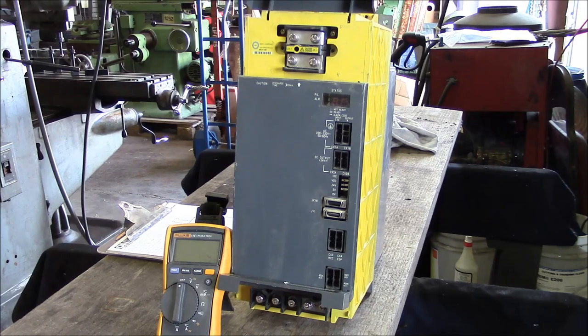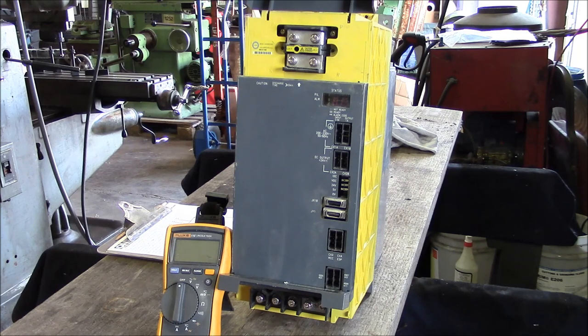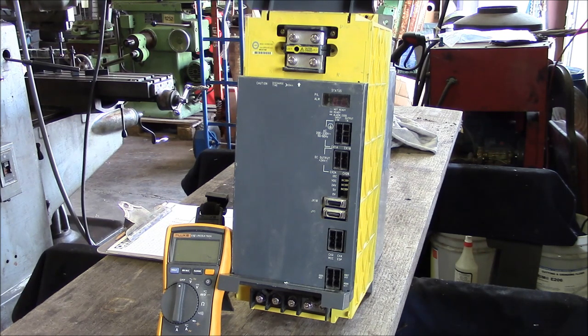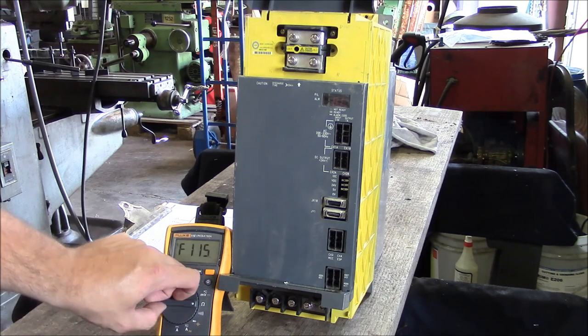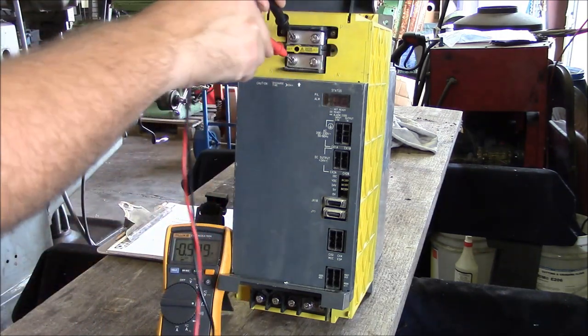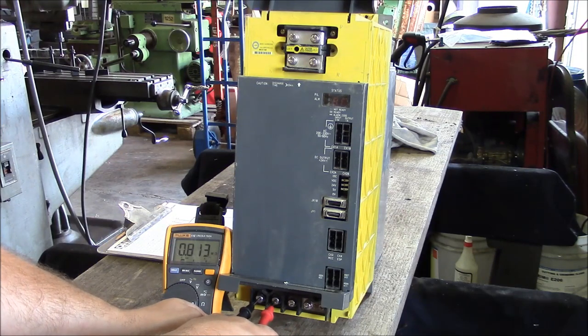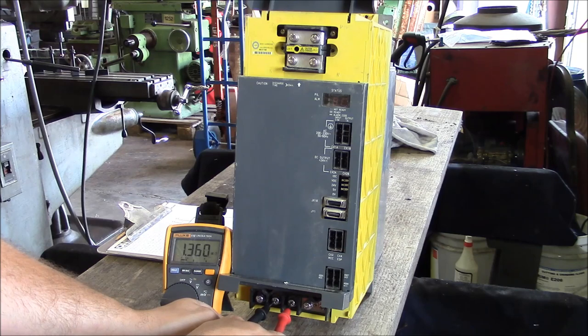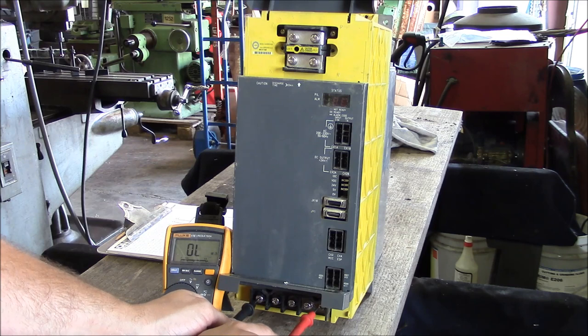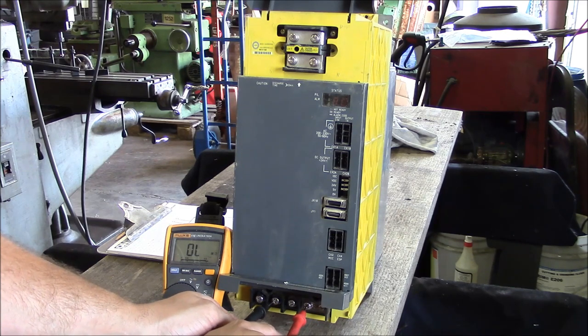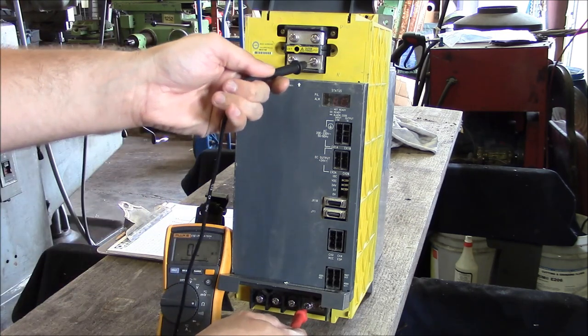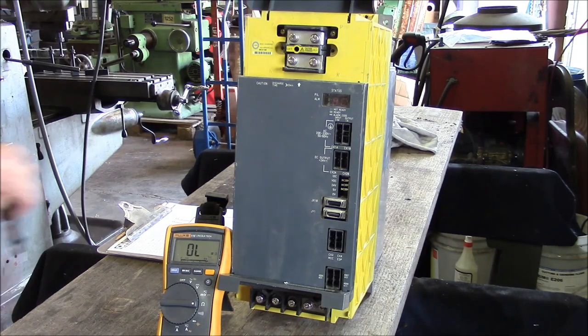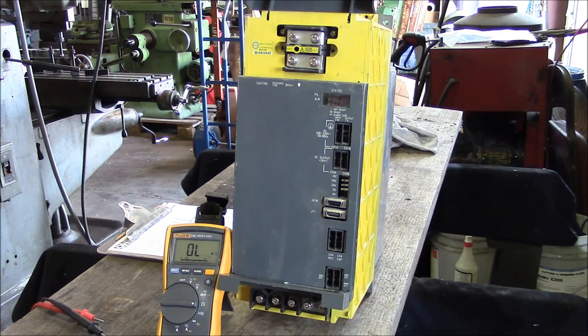Okay, so the first thing I'm going to do is check all the inputs and outputs to each other and to the ground, and the values here don't matter. It's just kind of a reality check to make sure nothing is shorted. So I'll set my meter for resistance and check across the DC bus. Good. L1, L2 fine. L2, L3 fine. L1, L3 fine. And then each one to ground - nothing, nothing, nothing. Okay, so we're good there. We don't have any dead shorts on the input or output side. So now it's time to test the diodes.